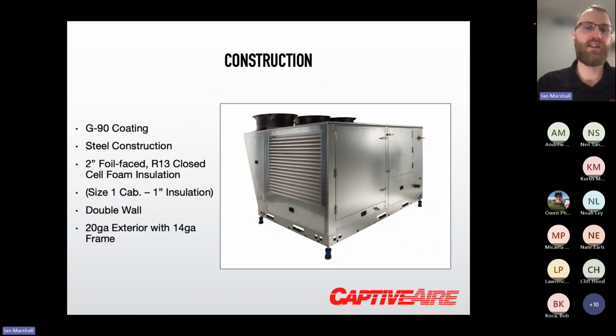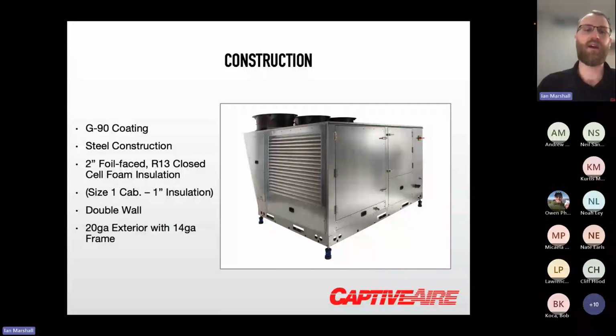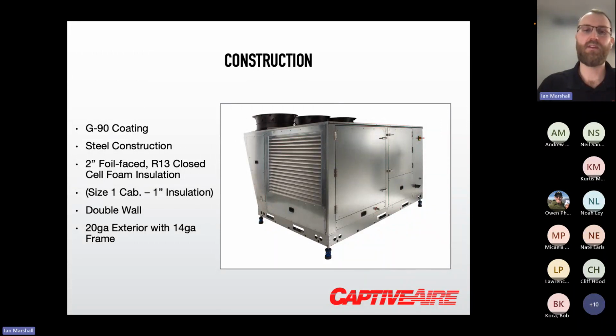Our standard unit construction is a little bit different than maybe some other manufacturers. It's a galvanized G90 double wall, so it's an interior and exterior. All of our cabinets are 2-inch R13 closed cell foam. Our smallest cabinet, size 1 cabinet, is actually 1 inch, but still double wall. And we've been utilizing galvanized G90 for rooftop equipment for years, and see this as our preferred approach for corrosion resistance, just given some of the challenges with painting and seeing paint chip and creating weak spots. That said, we do have an option to paint the cabinet if needed.